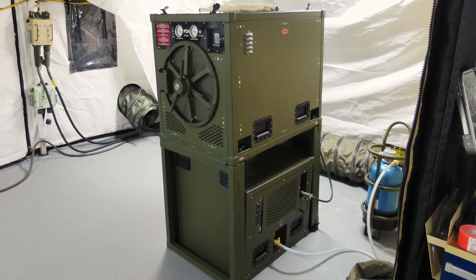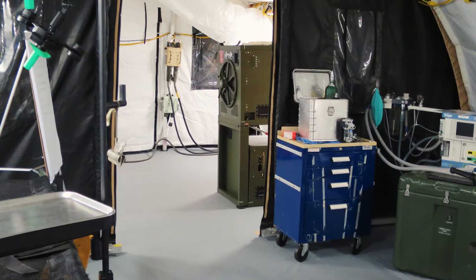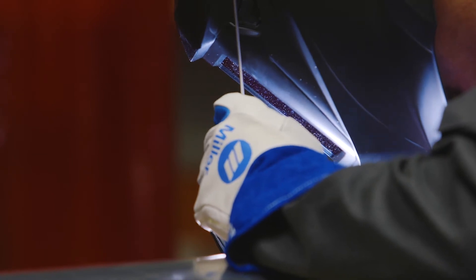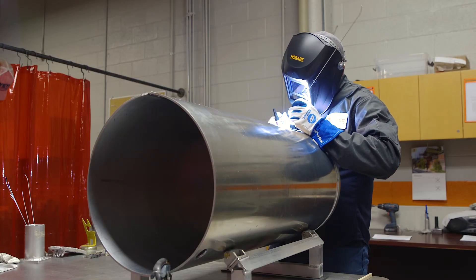It's specifically designed to be transported, so it's used in very harsh, austere environments, and that's why the entire sterilizer is made of aluminum. We weld to ASME code. We have everything from full penetration V-grooves to fillet welds, so we're under some very strict standards. We've got to stay focused on quality of our welds.